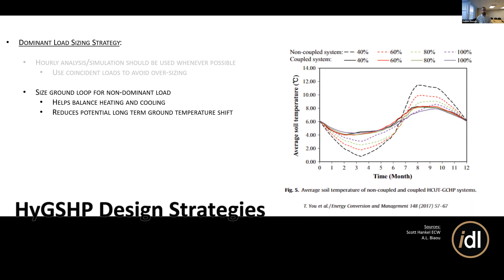And that's going to help balance out some of those soil temperatures, so you're not trying to pull heat from the ground all year long, and it's never going to be able to catch up. We'll pull heat part of the year, and then part of the year we'll push heat back in. So it's going to stay a little more even. So you're not going to have that long-term ground temperature shift, which might actually affect your capacity for the system. By doing that, you can really reduce your loop size by 20 to 40%.